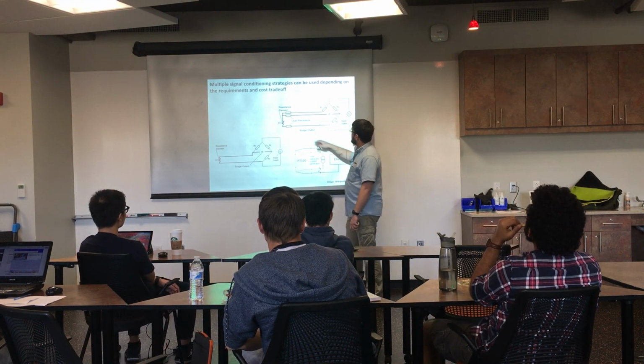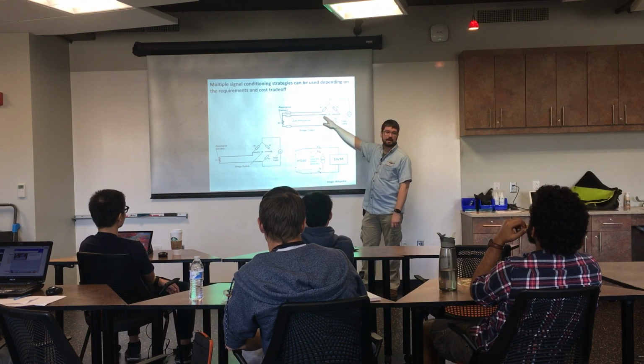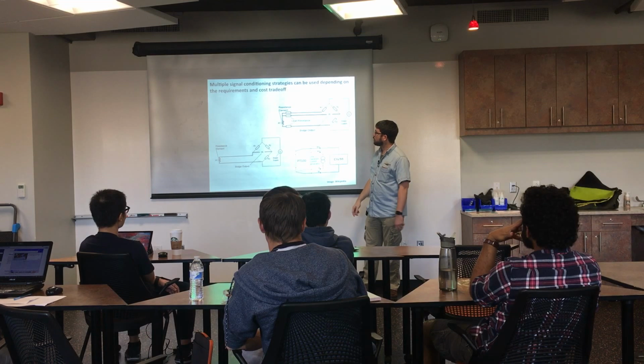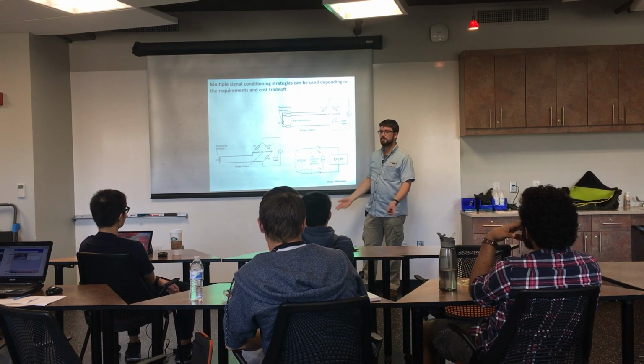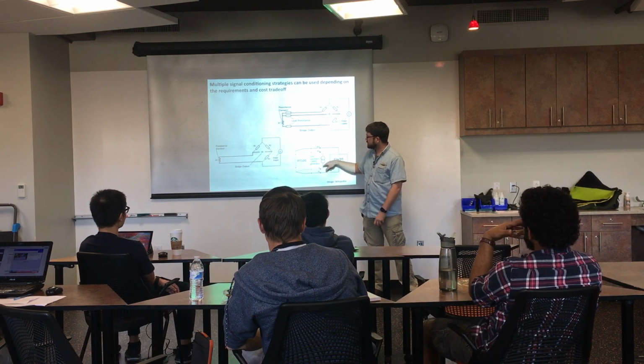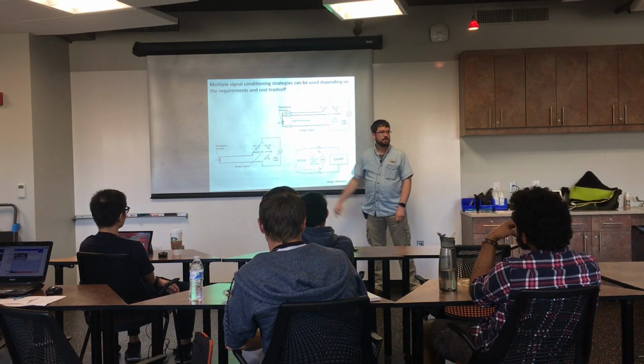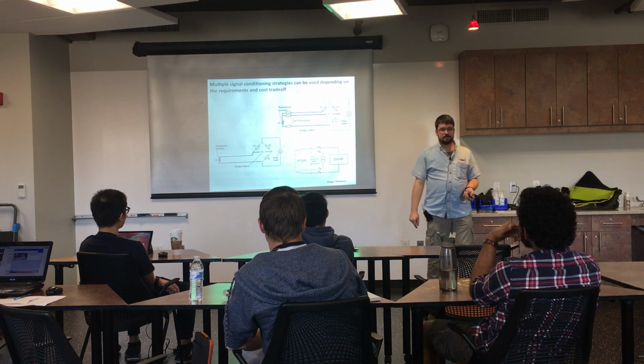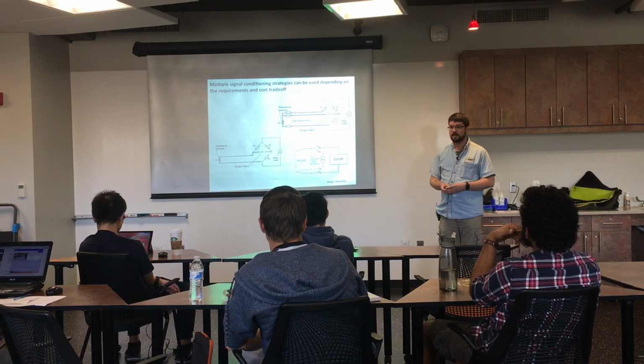To get around that, you end up running a third wire back to measure the voltage across the bridge, meaning more wires, more places for interference, and more places for things to break. Another way is to use a constant current source and measure the voltage drop across the RTD, then use Ohm's law to get the resistance.